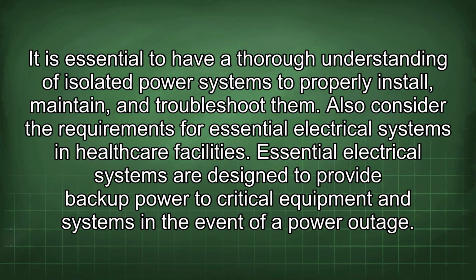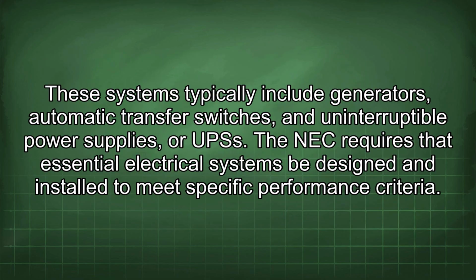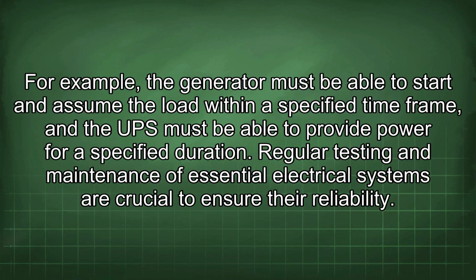Also consider the requirements for essential electrical systems in healthcare facilities. Essential electrical systems are designed to provide backup power to critical equipment and systems in the event of a power outage. These systems typically include generators, automatic transfer switches, and uninterruptible power supplies, or UPSs. The NEC requires that essential electrical systems be designed and installed to meet specific performance criteria. For example, the generator must be able to start and assume the load within a specified time frame, and the UPS must be able to provide power for a specified duration.